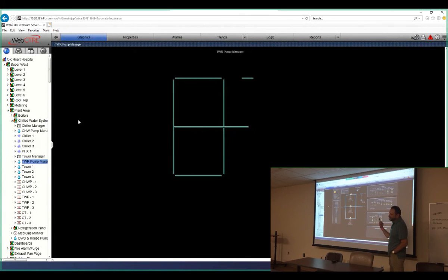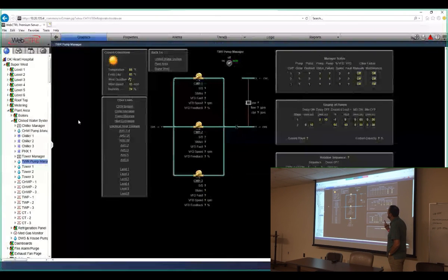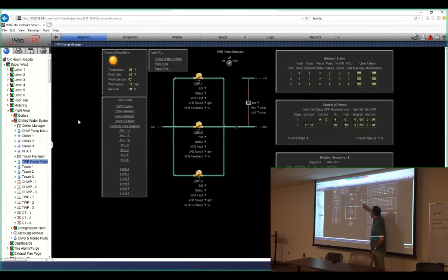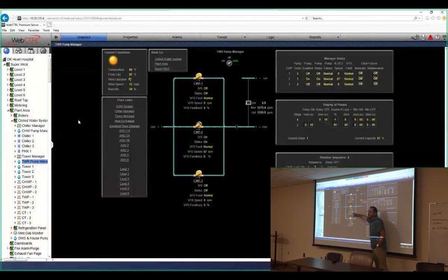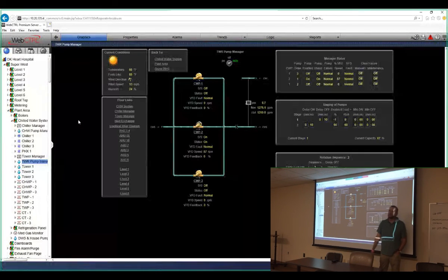So one machine is basically 1200 GPM. This condenser water pump speed is going to try to maintain differential pressure at a 1200 GPM set point. If we have just one chiller on, that's what it's going to track, this 1200 GPM. If you have two chillers on, it's going to track to 2400 GPM. And we need another cooling tower, because only one cooling tower can handle one machine and one condenser water pump.